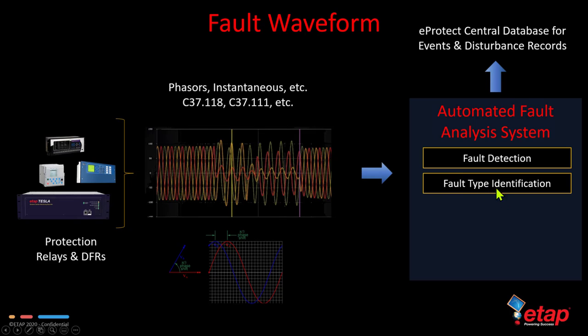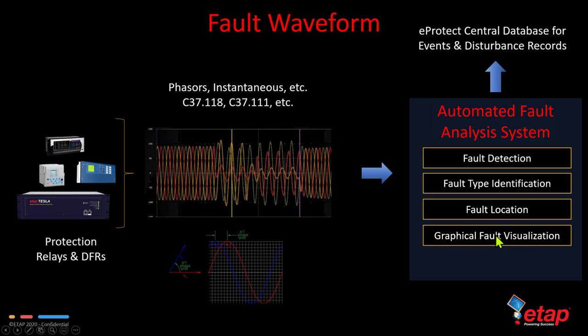in the network. Fault type identification, such as the fault type, whether it's phase-to-phase, phase-to-ground, and so on. The fault location, or essentially the fault distance, in case the relay does not provide the fault distance information, but more particularly to visualize that fault location graphically on the network model or the geospatial model. And once the fault location is visualized, you can then do the as operated versus as designed.